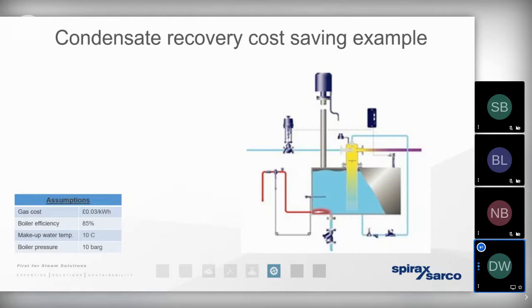But remember, if we're using that direct steam injection to keep the boiler feed water temperature at 85 degrees, that could be due to the fact that we've got a lot of condensate being dumped to waste that we're not aware of. In other words, we're consuming more steam than we actually think we are. So let's say we've walked around the distribution network and we've identified that we've got a failed condensate pump, or we could have a steam trap that's failed in the open position.